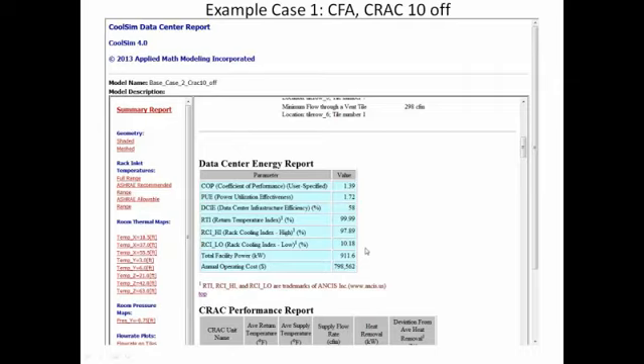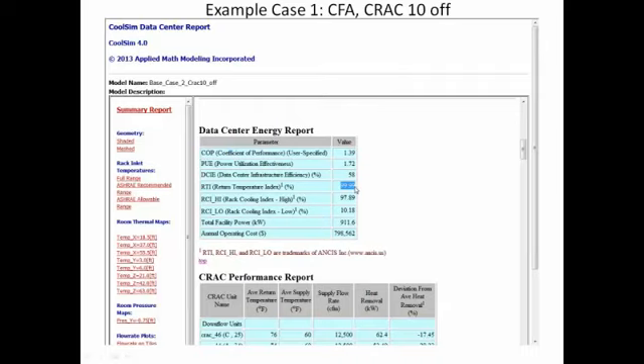reached a point that you're not wasting energy by fanning around a lot of air. At the same time, you're providing the actual recommended temperatures for the intakes to electronic equipment, and that can be equivalent to reliability of the equipment. That's correct. That's exactly correct. And they are an interplay. I mean, as you turn down RTI, you have to watch the others. And I think the direction you want to go is get the RTI as close as you can to where it should be. Match those racks as close as you can. Watch the RCI high to make sure you don't have any hot spots. And if you do, go find them with CFD and look at the plots and understand where it is. Right. And then begin to drive temperature up.